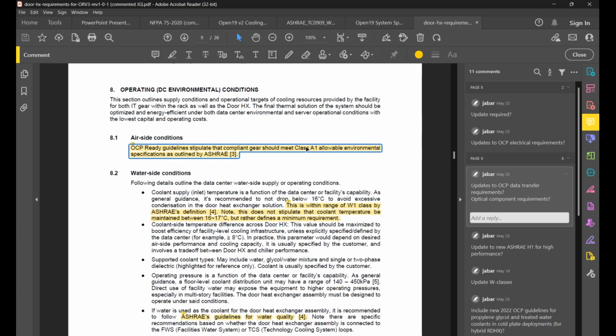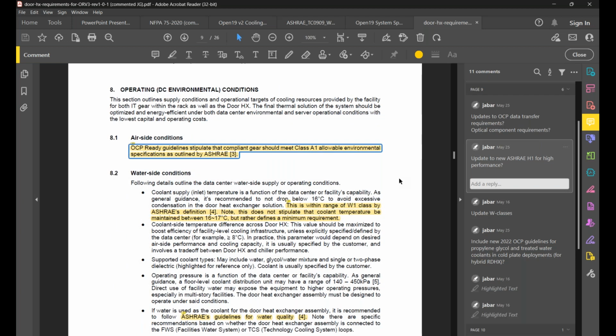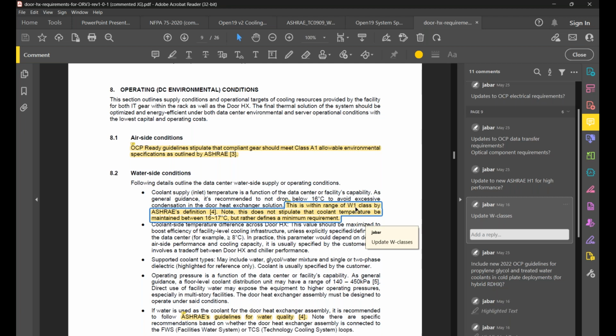The next comment was on the OCP ready guidelines, the class A1 - because there's been an update. There was an update from ASHRAE for HPC, if you're doing air cooled, so there's another category, and that might be something we need to update here. Also, this was using the old W class, like W1, 2, that was originally established by ASHRAE, and now we've updated it to the W17, 27, etc. We're actually referencing the water temperature maximum from 4 degrees to 17 or 27 or whatever your range is for your facility. So we need to update this as well.